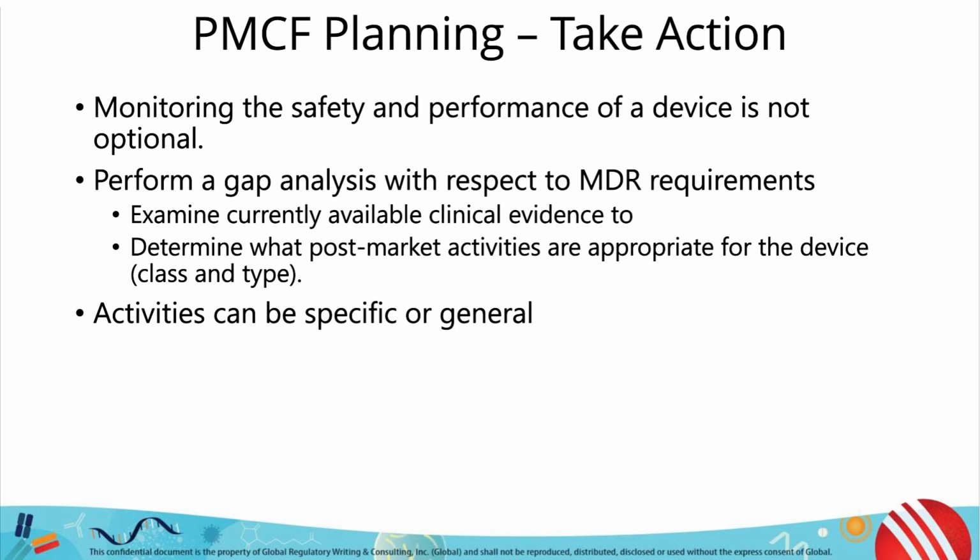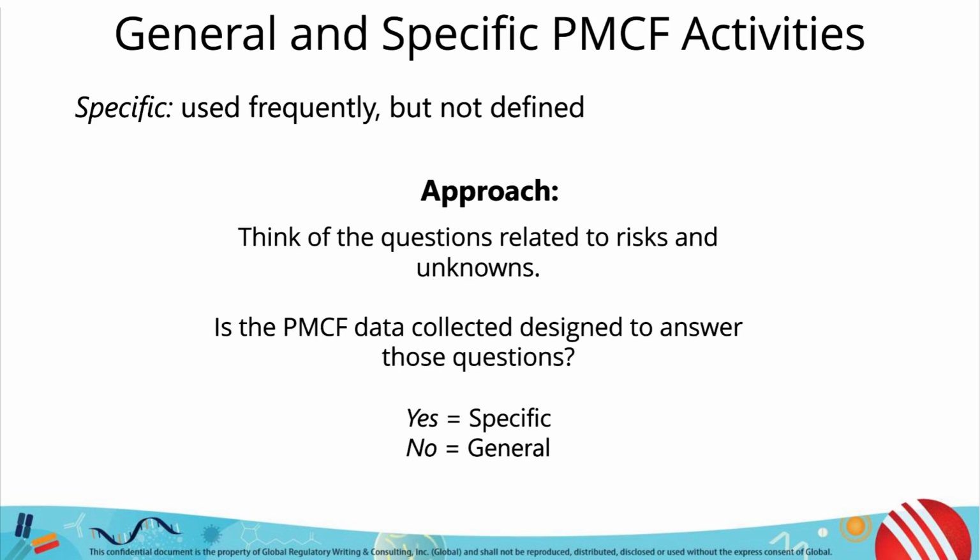PMCF activities can be specific or general. One of the trickier parts of interpreting the MDR is the use of the word specific. Specific is a word that is used frequently but is not defined. We can think of specific activities as those that are designed to answer specific questions about the device. If the PMCF data is designed to answer specific questions, then the activity is specific. If not, we would consider the activity to be general.